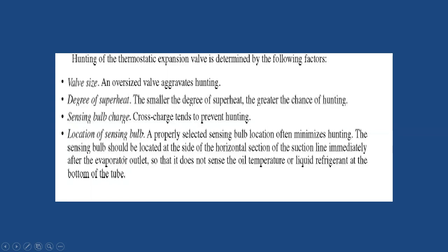To prevent hunting: use a properly sized valve; maintain a slightly higher degree of superheat; use cross charge; and locate the sensing bulb at the side of the horizontal suction line. These factors, when properly controlled, can prevent hunting effectively.